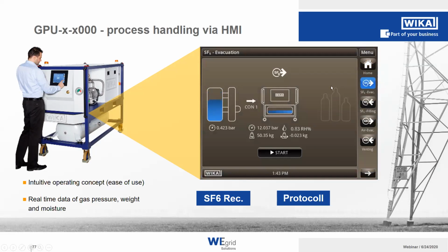For the SF6 evacuation, we see that we are getting the gas out through our connection at Con 1 into our internal storage. And we always get the information about the pressure in the compartment, as well as the pressure in our internal tank, the relative humidity level, and the weight of the gas as well. And we can easily start and stop it by clicking on the buttons on the very intuitive HMI interface.